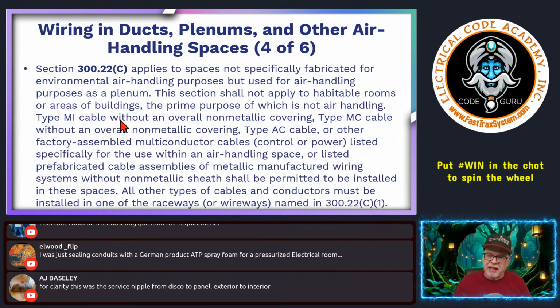Type MI cable without an overall non-metallic covering can be up there. Ain't nobody going to run MI, I'm just saying. MC cable without an overall non-metallic covering. And you'll notice this doesn't have to be smooth or corrugated. It could be the standard old interlock. So I get that question from people all the time. Can I have MC cable above a suspended ceiling that's being used for environmental air purposes? Does it have to be plenum rated? And the answer to that is absolutely not. Standard MC does not have to be plenum rated.